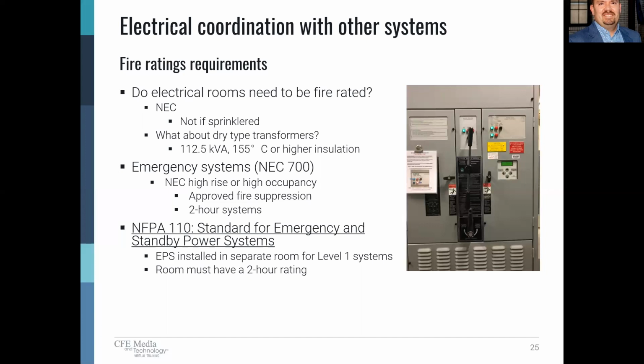Also, NFPA 110, the standard for emergency and standby power systems, requires that EPS system components be installed in separate rooms for Level 1 systems. A good example of this is a healthcare occupancy that has a Level 1 emergency generator system. The EPS piece is the automatic transfer switches. Those need to be in a separate dedicated room for that equipment. And that room must be 2-hour rated.